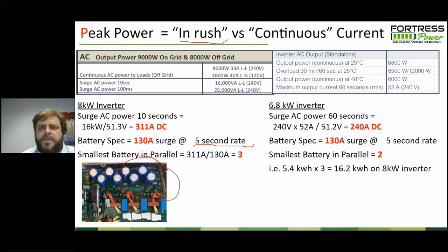The same capacitors that can discharge that electricity quickly will also suck up electricity quickly. And that can cause, for the very first time, when you're turning that inverter system on and those capacitors are empty, that inrush current just naturally flows into those capacitors and charges them up. And so you get into inrush errors when you are turning equipment on for the very first time, whether they be charge controllers or inverters, as well as other inrush instances for loads, like when a well pump is starting for a very brief period of time.